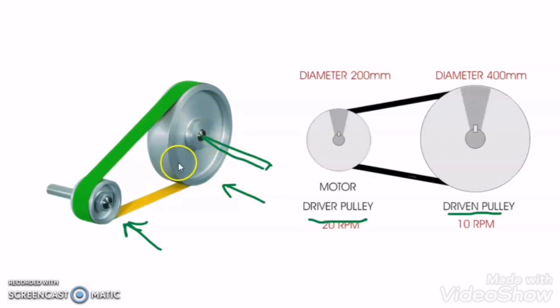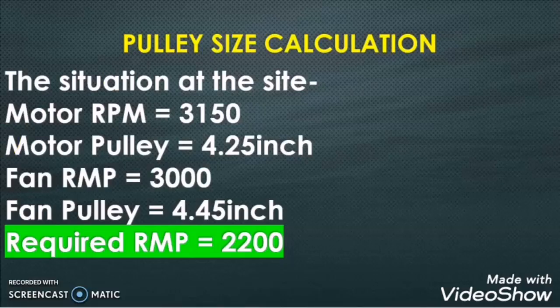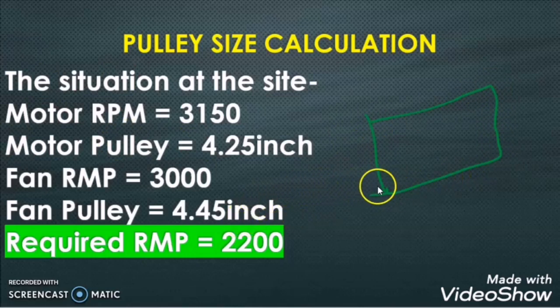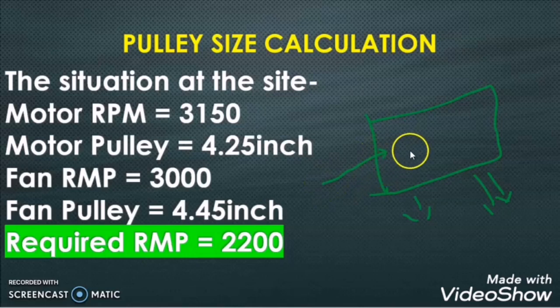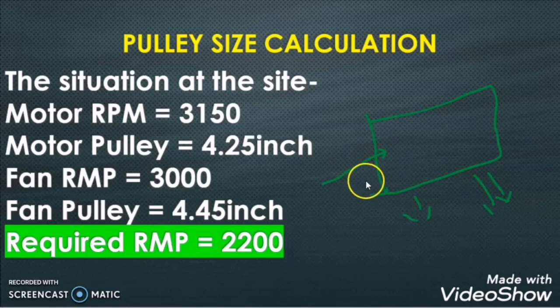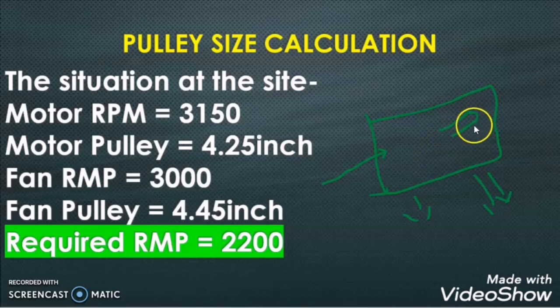Now let me explain what the problem was at site and how we solved it. We have one FAHU in our project. In that FAHU we were facing the problem of water leaking from the FAHU body. When we investigated the reason, we found that the motor RPM was very high and due to that the fan RPM was also very high, because the fan blades and the motor shaft are coupled with the pulley. So as the motor RPM was high, the fan blades RPM was also very high, and due to that the CFM — cubic feet per minute — airflow was very high.